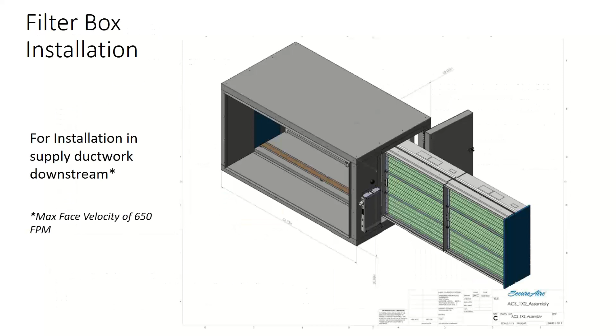One of the nice things about some of these kind of filters too, that use both electrical and filter media in conjunction with one another, is that the filters can last longer. For example, like I said, I have a similar technology at my own home, and my filter's been in for 4 years, and I've changed it 4 times. The first time it was 13 months, then 9 months, then 11 months, then 15 months. I change it based on pressure drop.